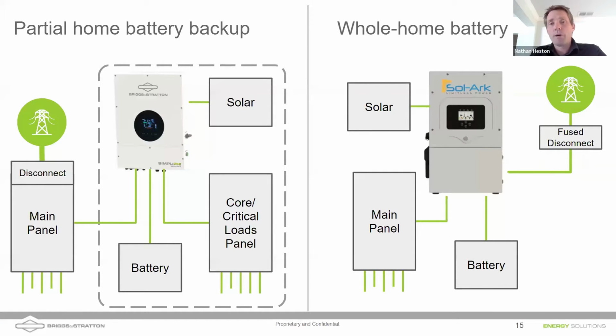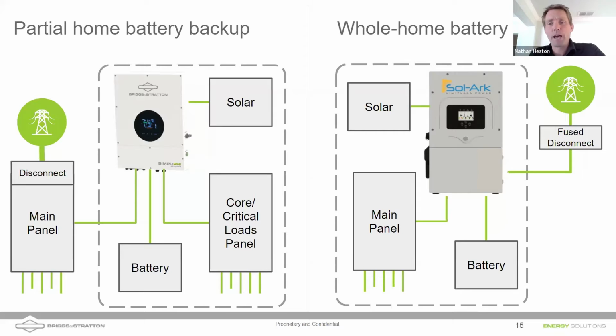And then in the event of a grid down situation, that battery will power the entire loads panel. Now, we should keep in mind the Sol-Ark 15K is capable of pulling 200 amps from the grid and passing that through to the main loads panel. But when operating off of batteries and solar, we're much more limited. Off of batteries alone, we're at 60 amps at 240 AC. So keep in mind, when we're saying whole home backup, we don't necessarily mean that there's enough power to run your entire home if you're really going to slam your home with 200 amps.